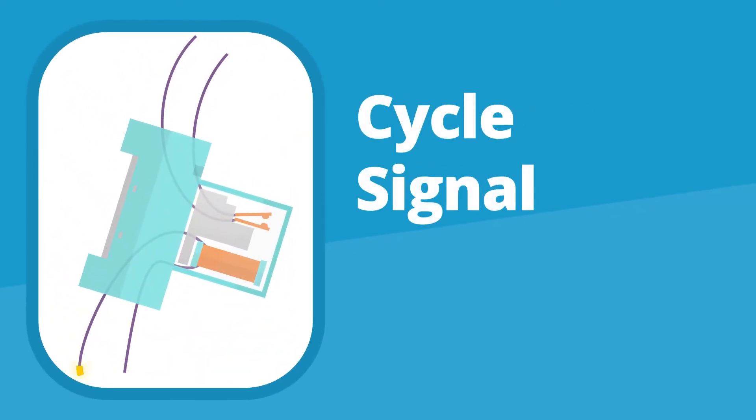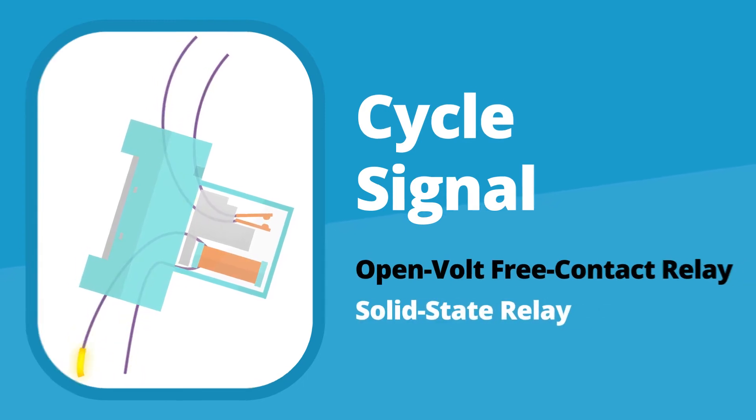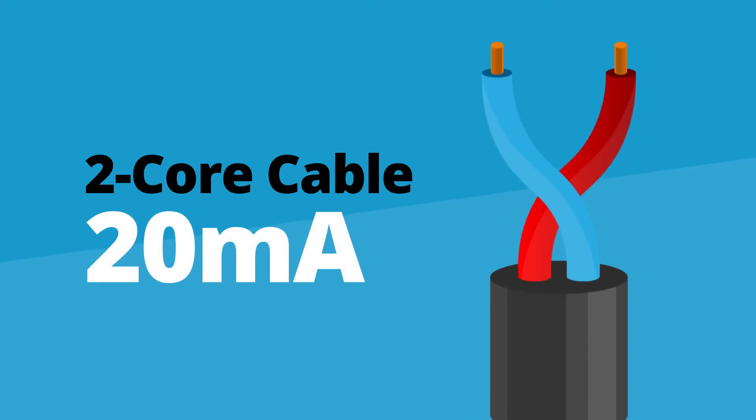The XTX module requires a cycle signal from each machine, provided by either an open volt free contact relay or a solid state relay, using any two core cable that is capable of carrying 20 milliamps or more.